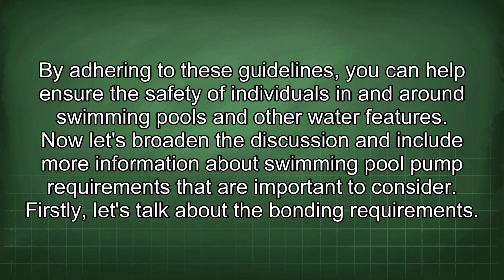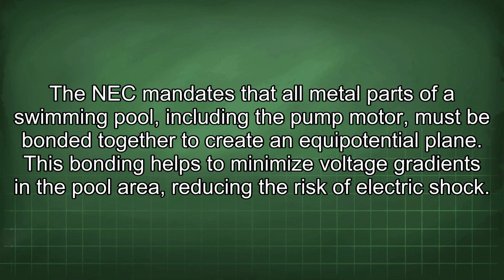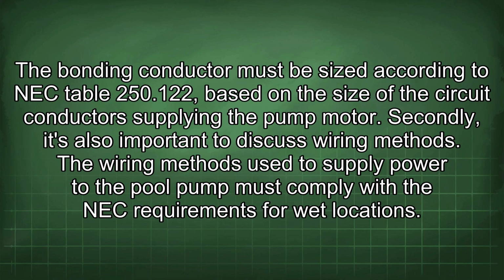Now let's broaden the discussion and include more information about swimming pool pump requirements that are important to consider. Firstly, let's talk about the bonding requirements. The NEC mandates that all metal parts of a swimming pool, including the pump motor, must be bonded together to create an equipotential plane. This bonding helps to minimize voltage gradients in the pool area, reducing the risk of electric shock. The bonding conductor must be sized according to NEC Table 250.122, based on the size of the circuit conductors supplying the pump motor.